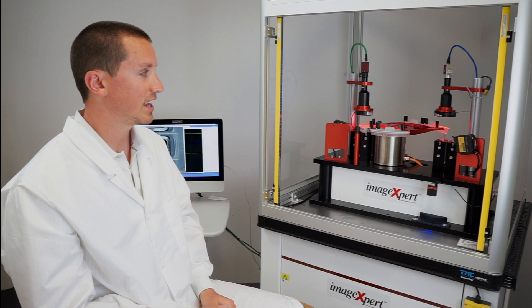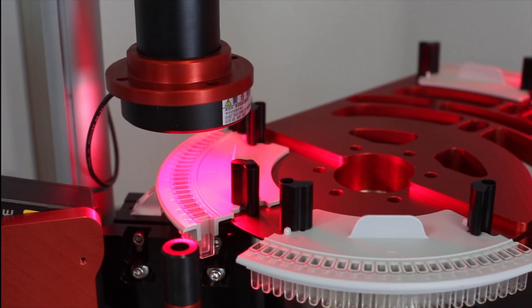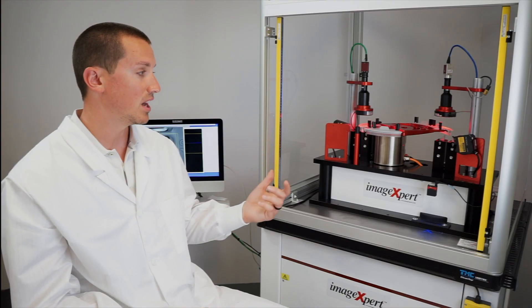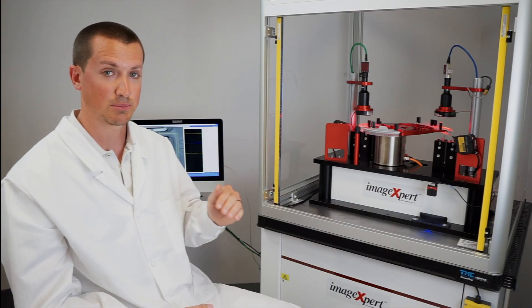The third inspection position has a camera that looks at the cuvette from the top, checking the integrity of the part as well as the integrity of the bond between the cuvette and the segment surface.